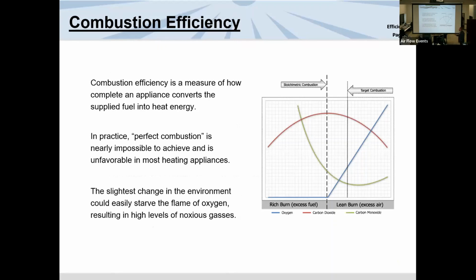Combustion efficiency. How well do we burn the gas relative to the oxygen supply, right? And that's a chart right there that the combustion engineers could understand, the gas engineers. It's called stoichiometric combustion, perfect combustion. The exact amount of air molecules are there for the gas that's being supplied. And what we want to keep in mind is that while perfect combustion is good in theory, the minute you get a little bit of debris on the fan or you get a bird's nest in the system, you run off that cliff and you start creating very poor combustion, which is bad. So this chart would be what my combustion engineers look at closely.